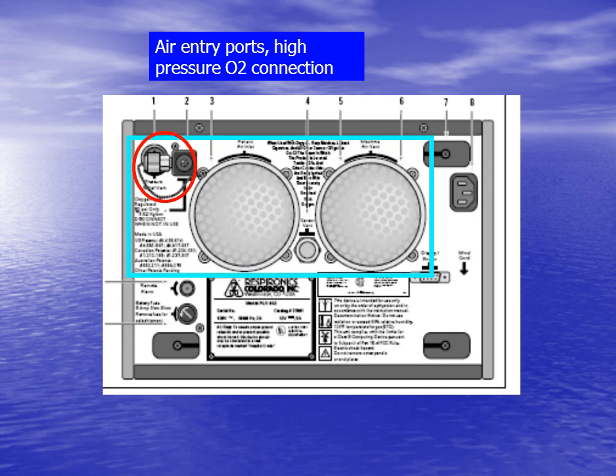Do not block the rear air entry ports of this ventilator, as it will interfere with its function. Filters cover these air entry ports. Clean the filters, which cover the ports, by running them under tap water and pressing them between towels twice a week. The filters are round, reusable foam.